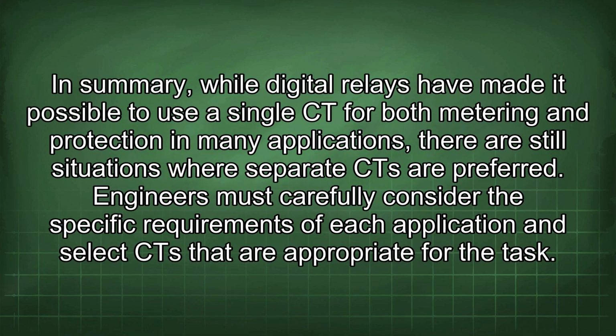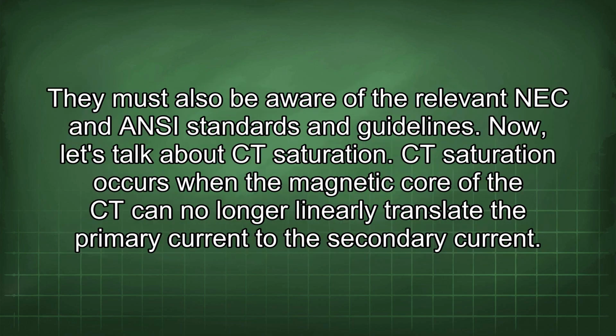In summary, while digital relays have made it possible to use a single CT for both metering and protection in many applications, there are still situations where separate CT are preferred. Engineers must carefully consider the specific requirements of each application and select CT that are appropriate for the task. They must also be aware of the relevant NEC and ANSI standards and guidelines. Now let's talk about CT saturation.